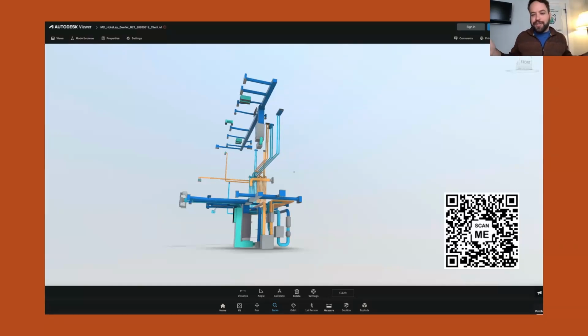If you want to understand the system types here, we went with Mitsubishi heat pumps - I think a P series and an M series on this. The P series is a hyperheat unit. We did the Zehnder ERV, and what was at the time called an Ultra Air, now called Santa Fe 70H dehumidifier. The makeup air system is a Fantech system. What am I leaving out, guys? I think it's metal ductwork - the only times we really like to use flex duct are the last few feet of a runout, to avoid vibration noise transference from a unit to a register.